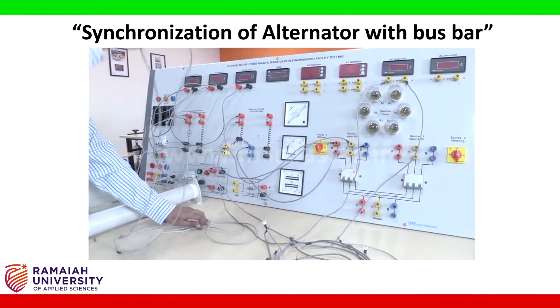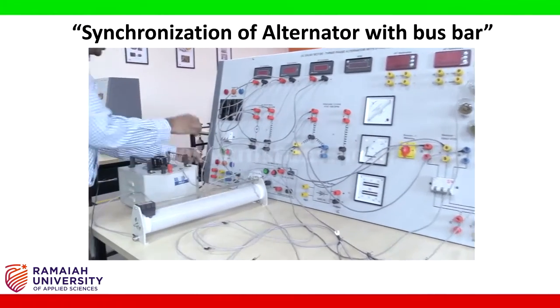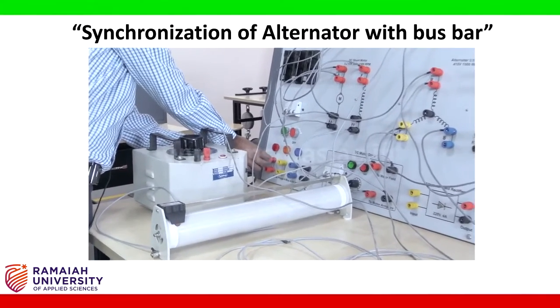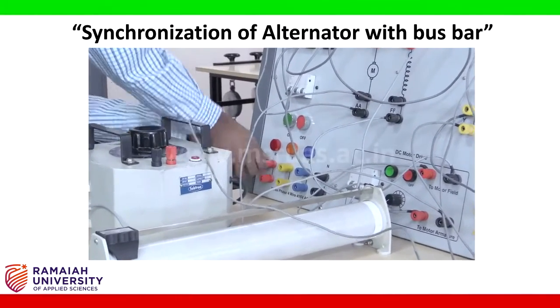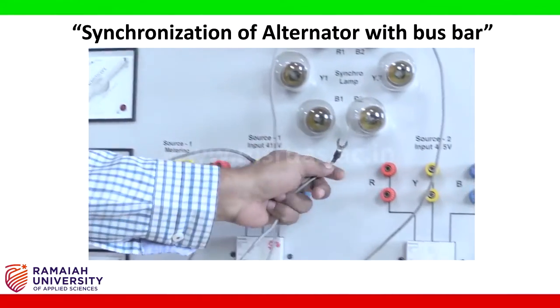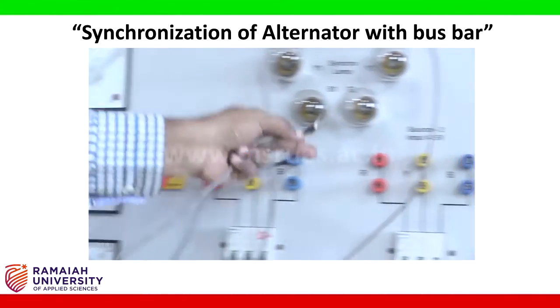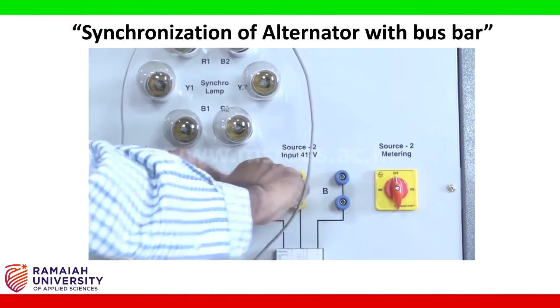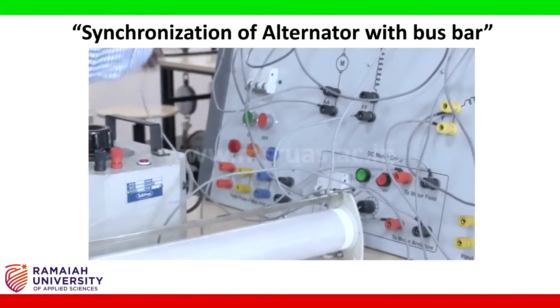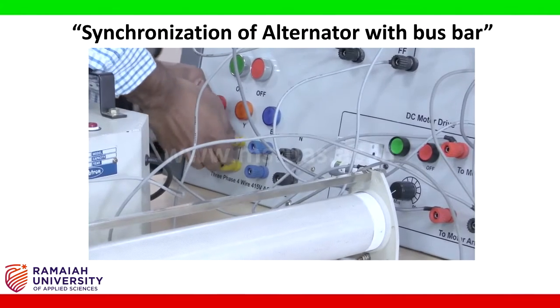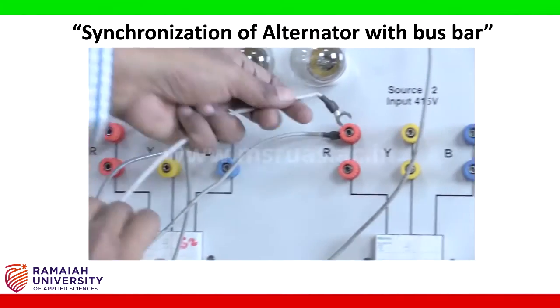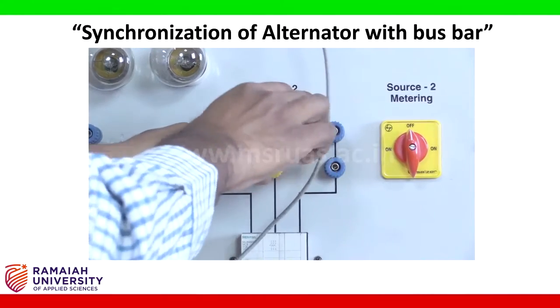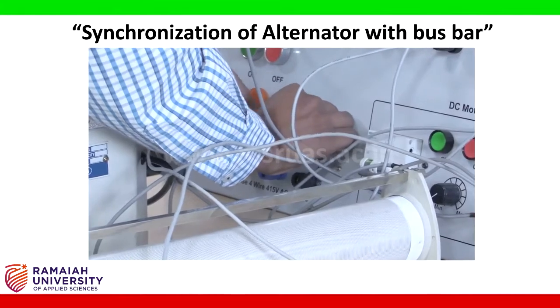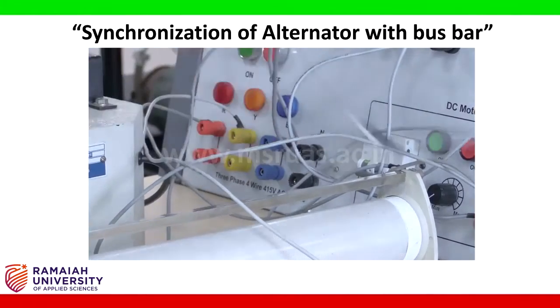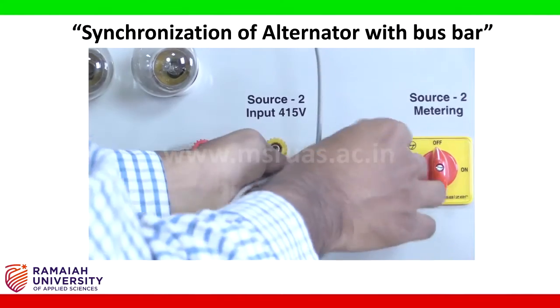Now take three long wires and connect the system voltage. That means the power system terminals we are bringing to our synchronization panel. R terminal of the input is given to the R terminal of the synchronizing panel. Similarly, Y terminal of the input supply is given to the Y terminal here. Take one more wire and connect from B terminal to the B terminal of the synchronizing panel.